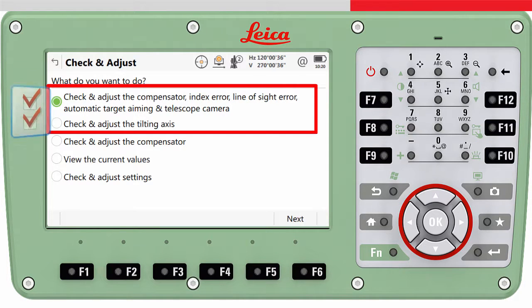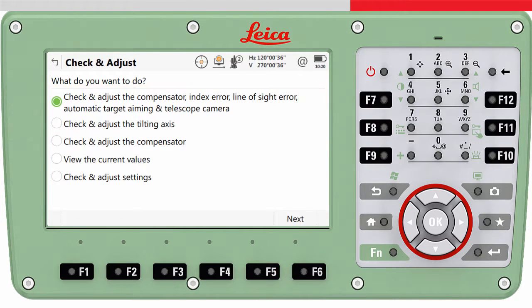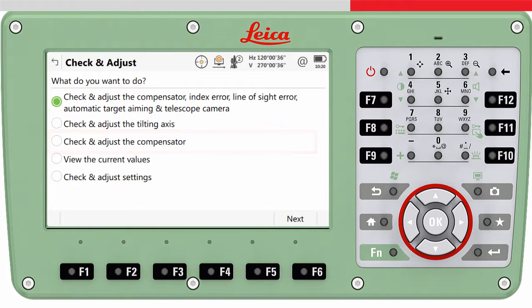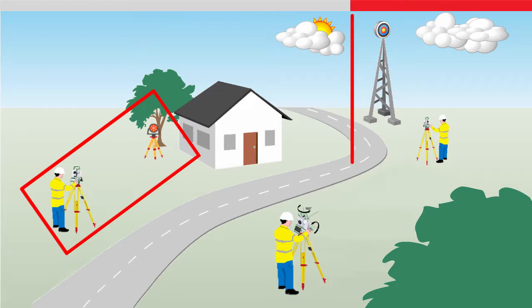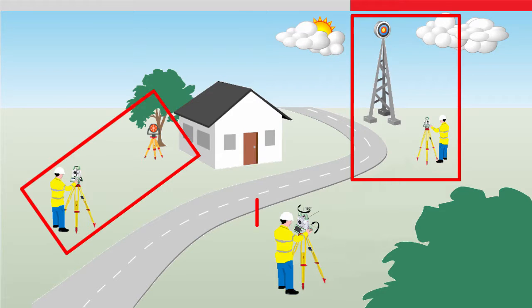Completing the first two routines will check and adjust all possible error sources. The third routine calibrates the inclination compensator only, which is not necessary if the combined calibration routine was executed before.